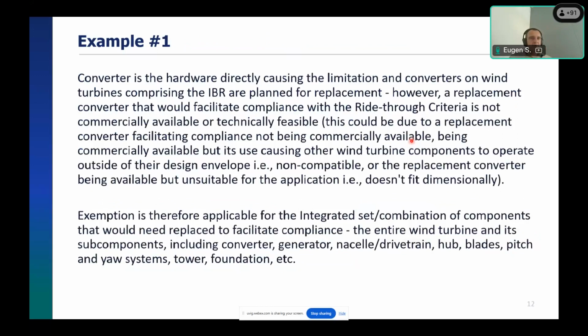One example is when we're looking at the wind turbine generator. For example, we need to do a replacement, either planned or after a failure. In some cases, if we replace the hardware with new hardware that complies with PRC 029, it might not be possible because such hardware is not available. And even if the hardware is available, it does not mean it will fit into this wind turbine generator, due to, for example, mechanical limitations.